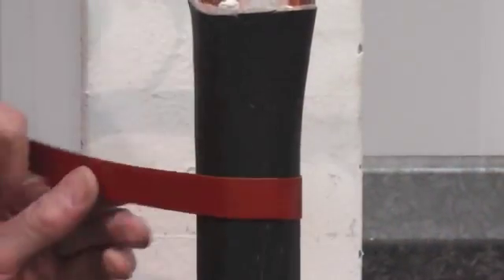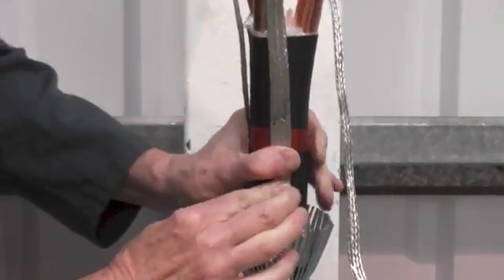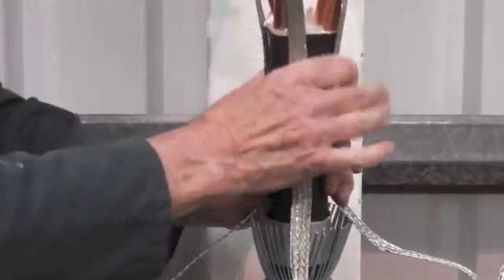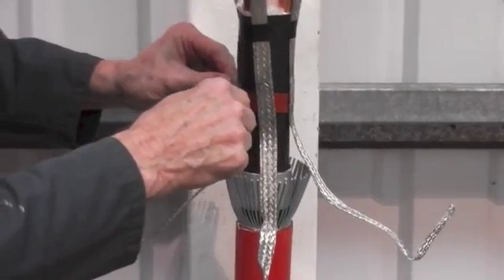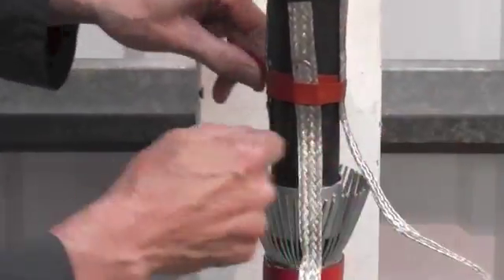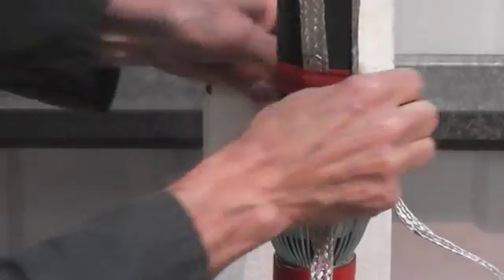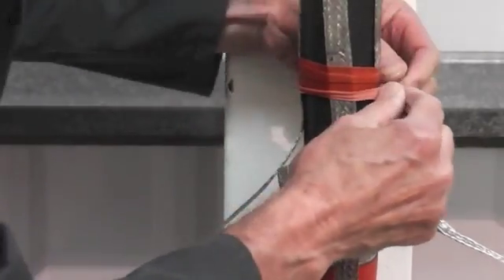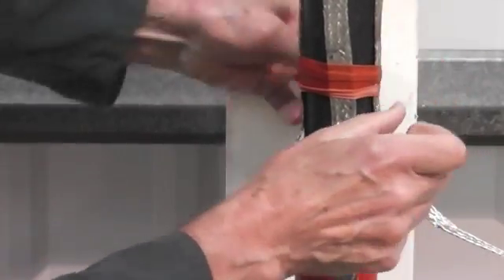Now wrap some red mastic tape around the outer cable jacket and position the earth braids with the solder blocks sitting on top of the mastic tape. Apply some further mastic tape over the top of the solder block, and this will stop the capillary action of water rising up the braids into the earth bond area.